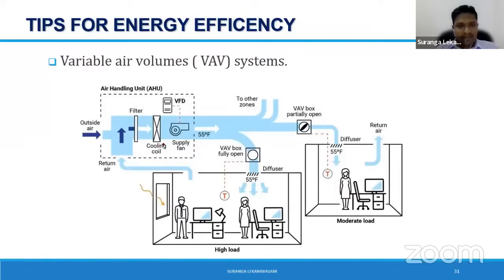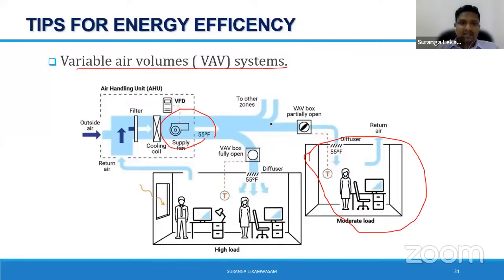Then variable air volume. You may have a single AHU feeding multiple zones, right? Let's say in the evening in your office, there may be very few people in one cubicle or one section or one zone. In another zone, there may be no people. So rather than supplying the same airflow rate through your AHU blower, you can vary the airflow rate with the use of VAV controls. It can be a VAV box, it can be a motorized damper based on the temperature. Whatever it is, you can run your AHU blower on a VFD rather than running it as CAV. So you have to think of variable air volume, which will substantially save energy because it's a square law saving, as I told you before.